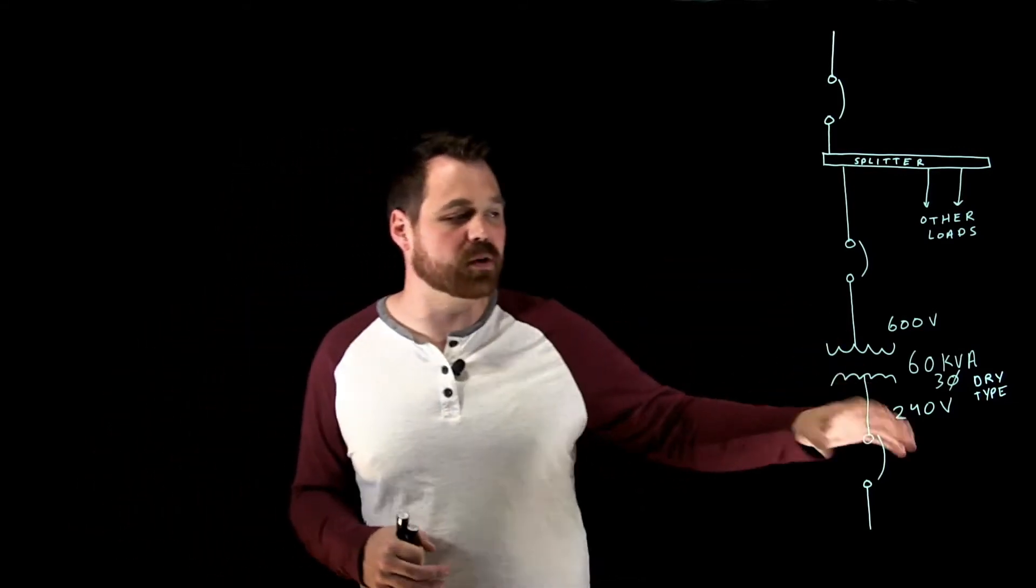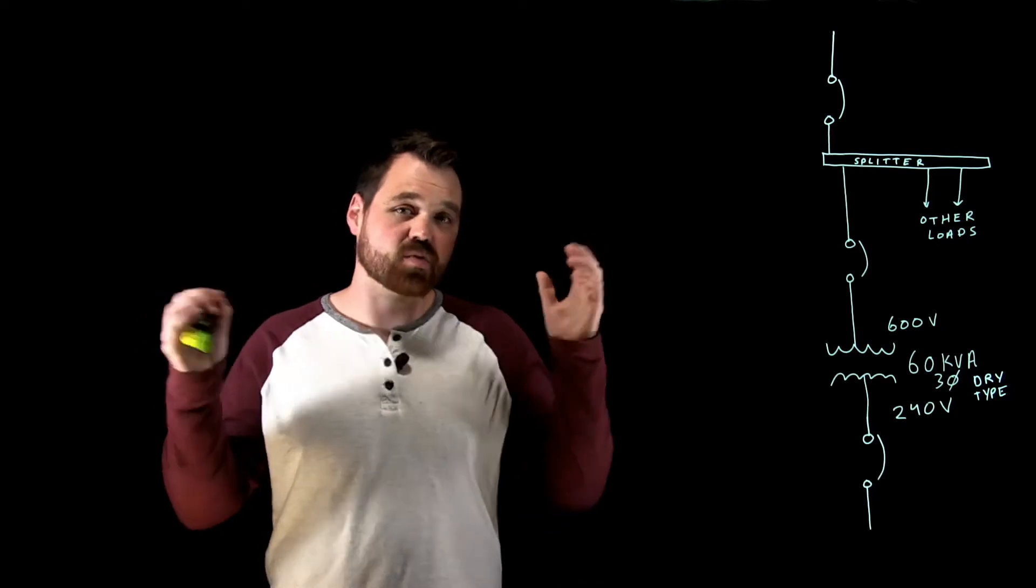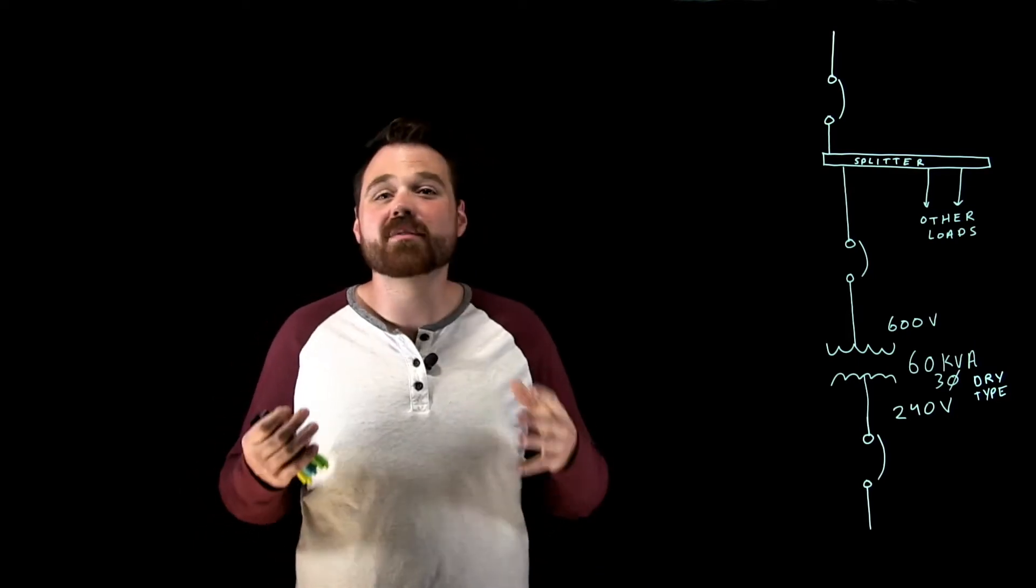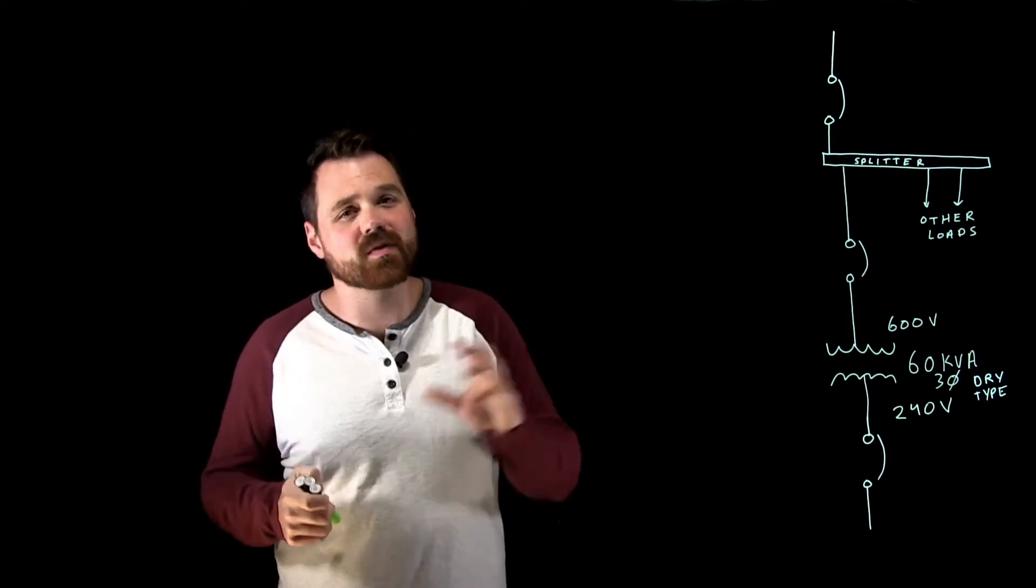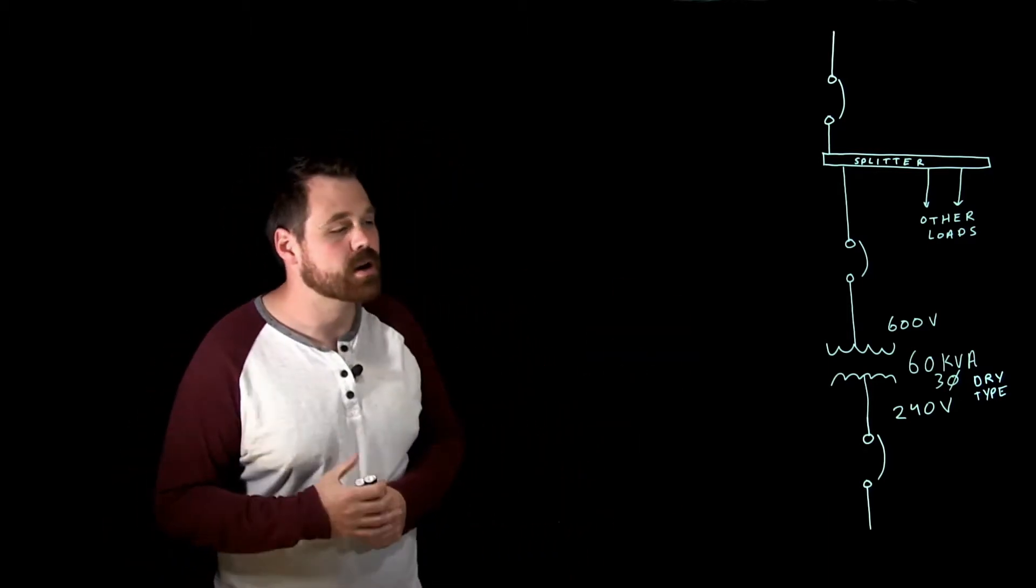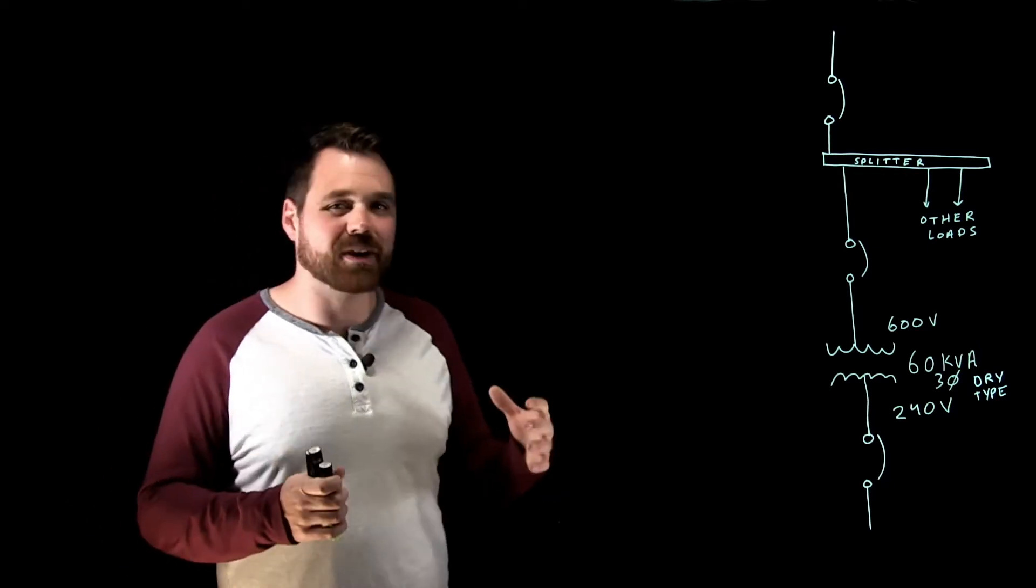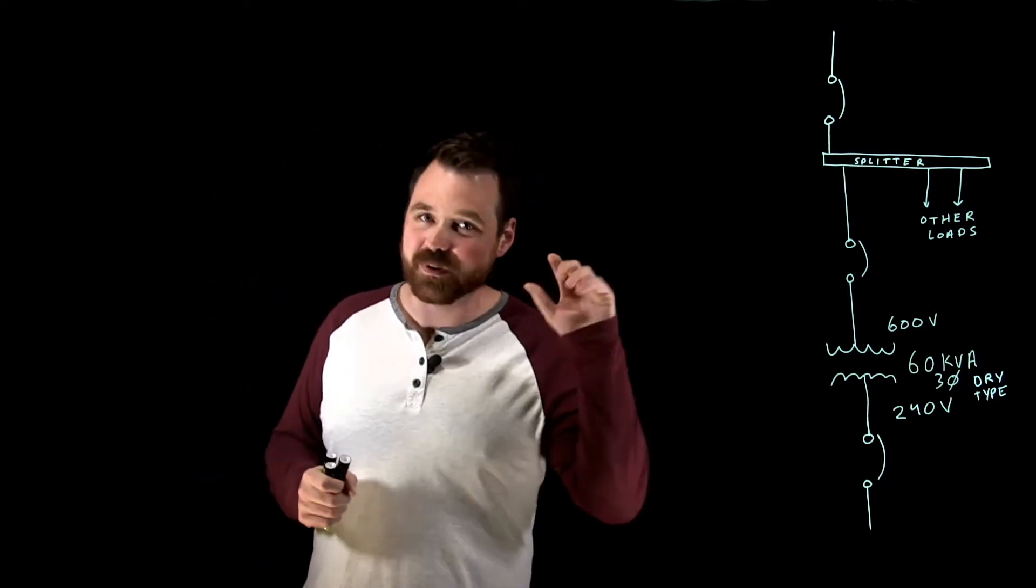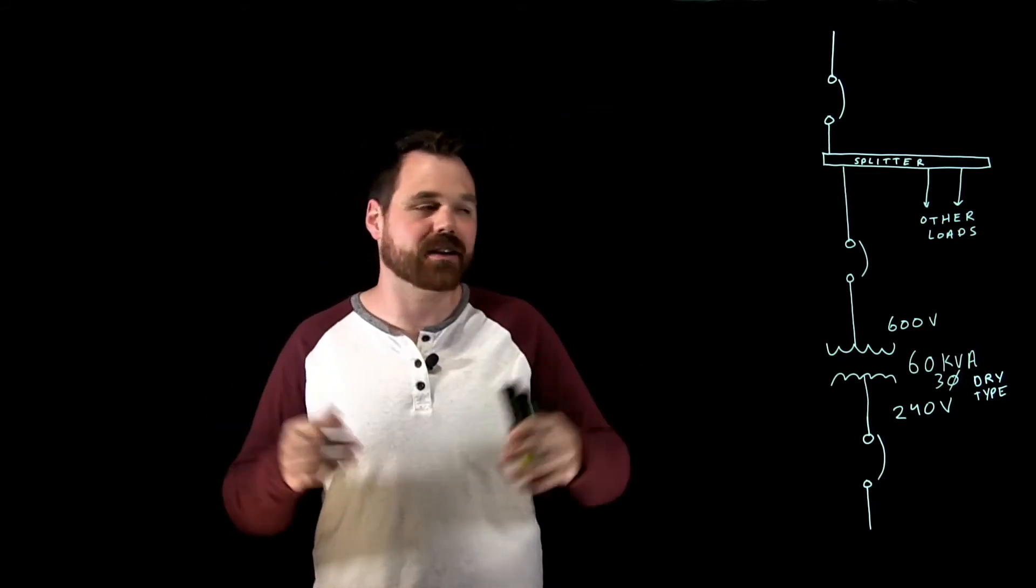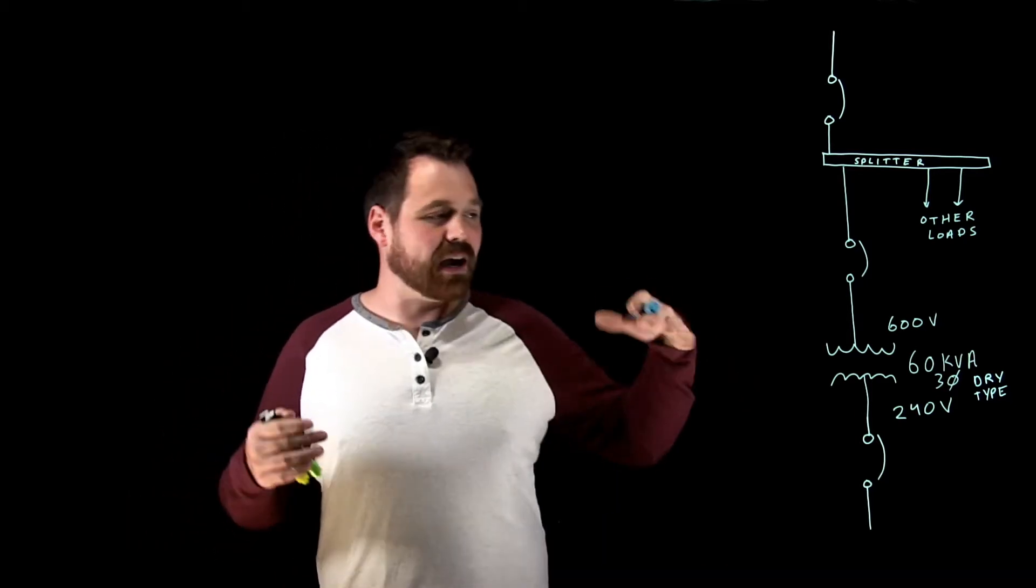We're going to use this one as an example and cover all the rules that go along with sizing that overcurrent device. It is just one rule in our code book. The biggest thing with all transformer rules and calculations for overcurrents - this is the most common type in the actual installation field - is you want to make sure you read the whole rule. Don't just read one sub rule and think you're done because they sneak up on you. There's sub rules way down that'll apply.